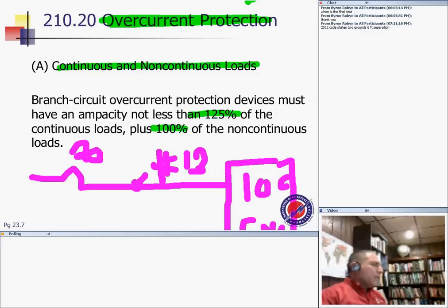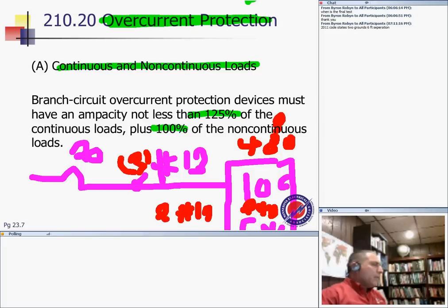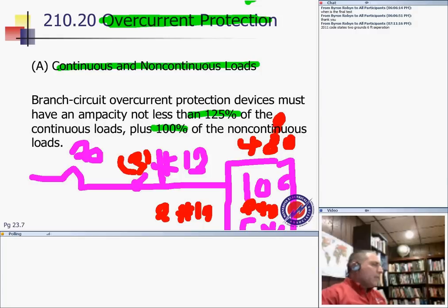Now the question would be, my friend Chad, how many of these conductors do I need? Well, tell me what the voltage is. Suppose this system was 480 volt, 3 phase, then I need 3 conductors. Suppose this system was 240, then I need 2 conductors. Of course. So this is the system. Okay, that's for continuous. Any question guys about branch circuits?